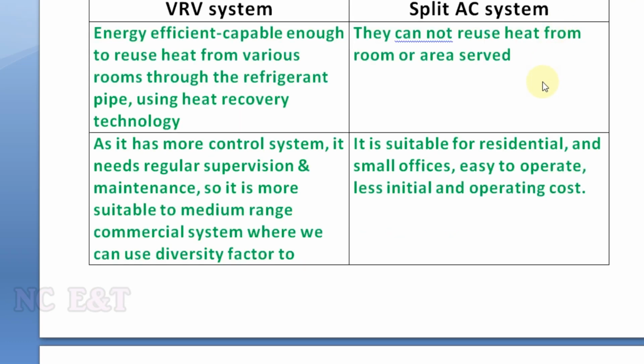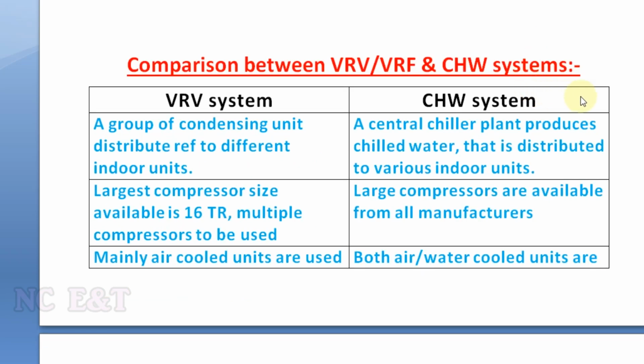As the VRF system has more control systems, it needs regular supervision and maintenance, so it is more suitable for medium range commercial systems where we have a permanent group for operation and maintenance. But split AC is suitable for residential and small offices, as it is easy to operate and has less initial cost and operating cost. Now we compare it with the chilled water system. Number 1, a group of condensing units distribute refrigerant to different indoor units, whereas in the chilled water system a central chiller plant produces chilled water that is distributed to various indoor units.